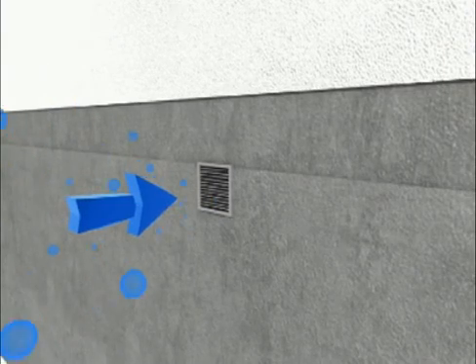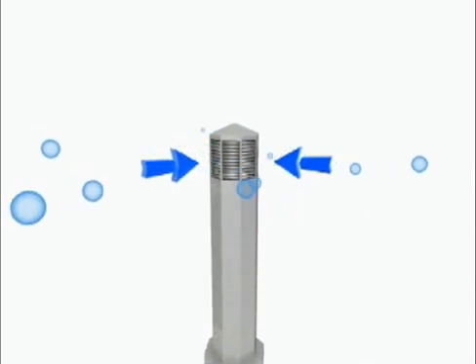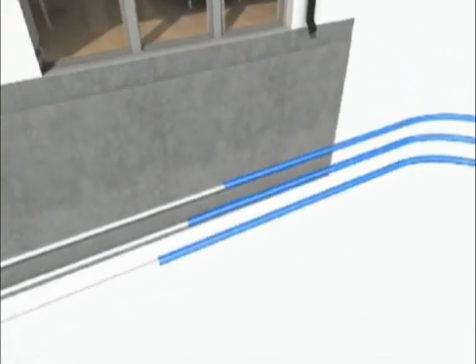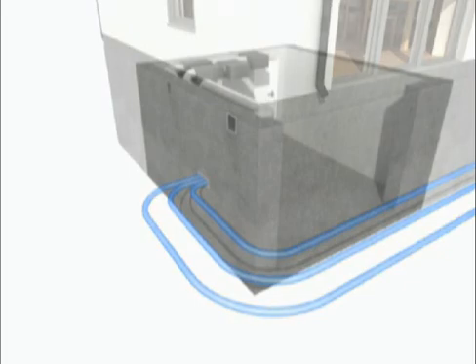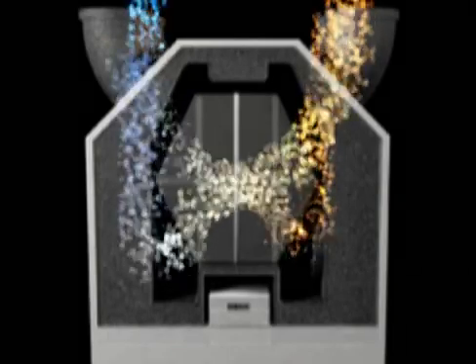This is how Zehnder Comfort Systems operates. The external air is taken through an intake unit into a ventilation device, or can optionally flow through an external geothermal heat exchanger. The fresh intake air is filtered and heated in the ventilation device by an integrated heat exchanger, which recovers up to 90% of the energy from the warm stale air.